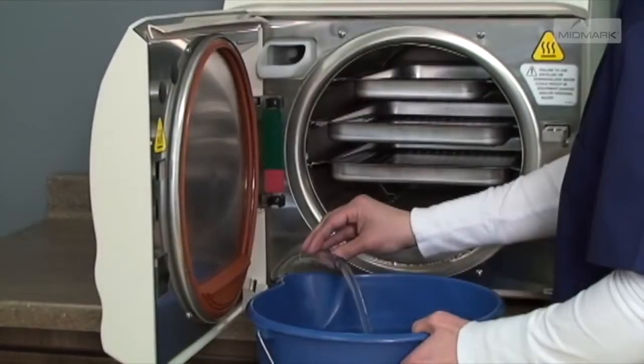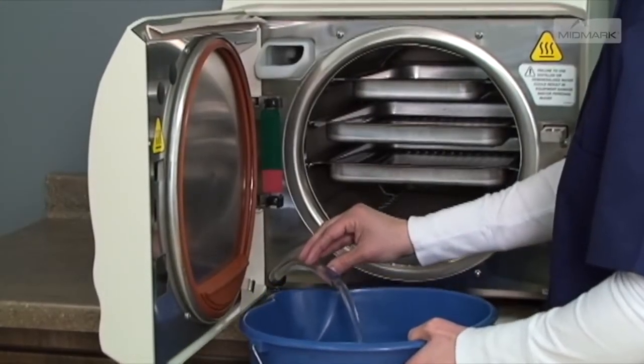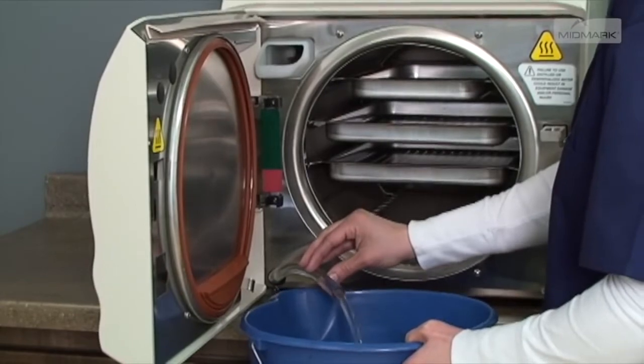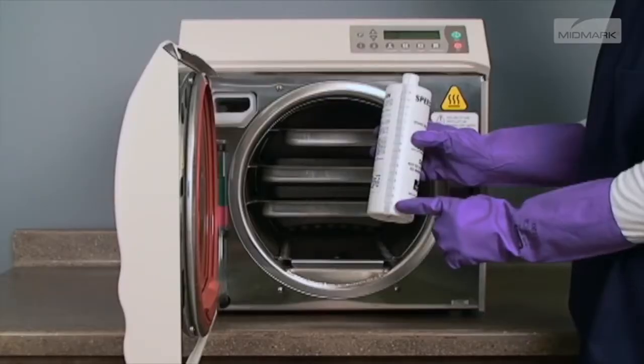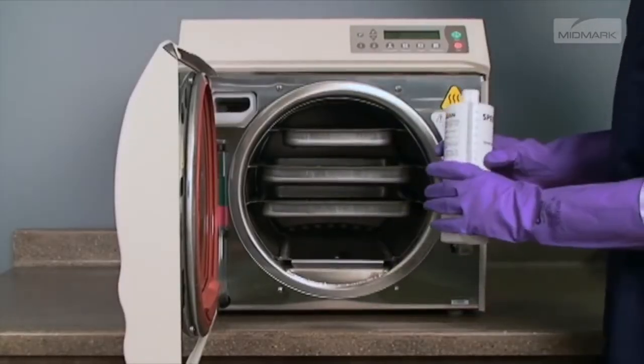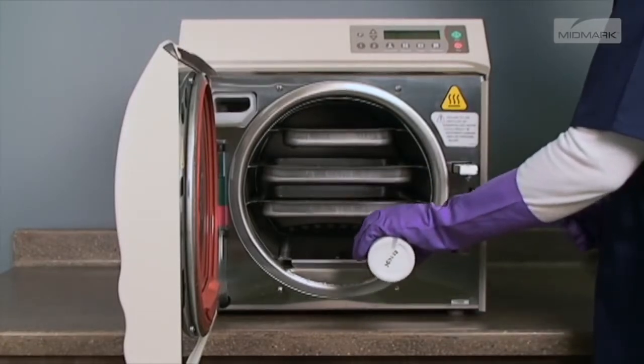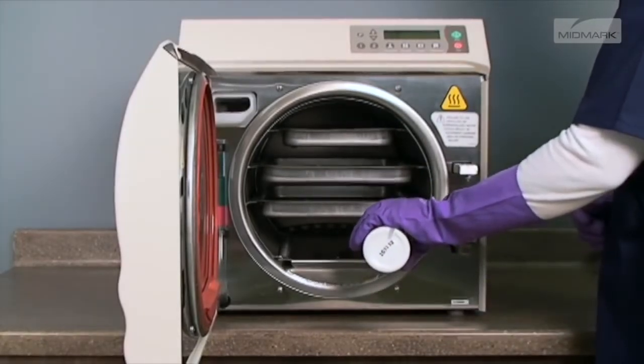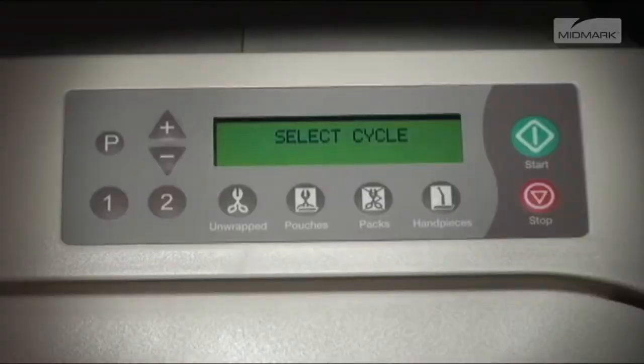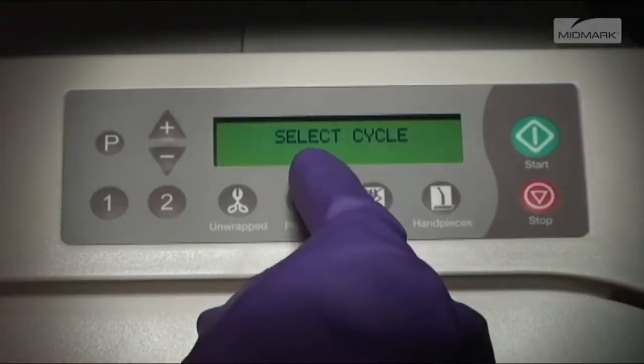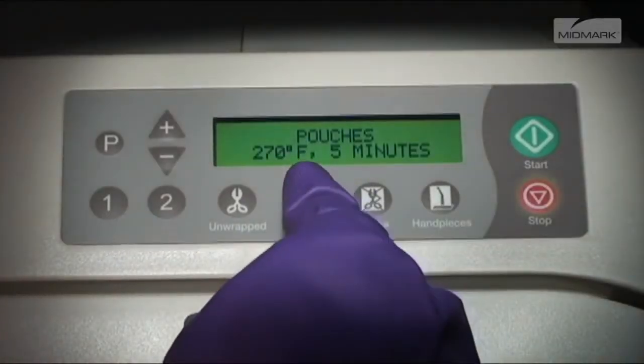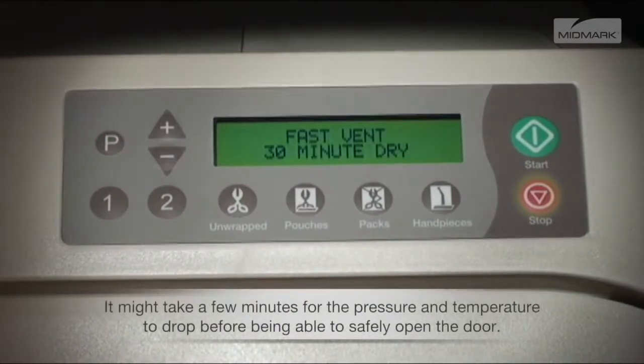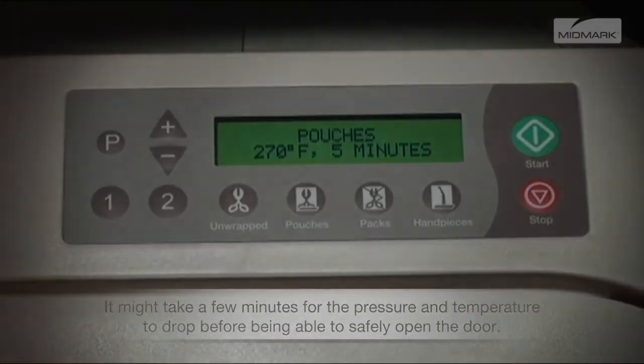Clean the chamber and plumbing. With a cool chamber, drain the autoclave's reservoir and refill with distilled water. Add 1 ounce of Speed Clean autoclave cleaner directly to the cool chamber. This is where you load your instruments for sterilization. Run 1 pouches cycle, but push the stop button when the drying cycle begins. It's not necessary for the dry cycle to run during this maintenance.